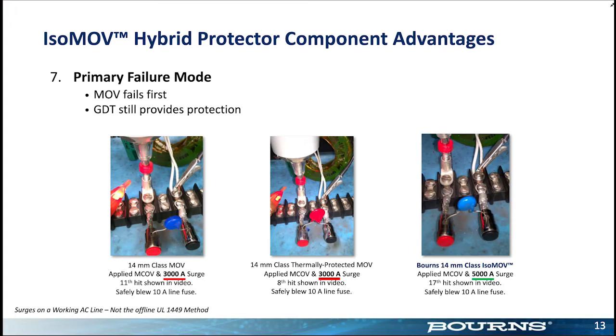So now I'm going to show another movie with the three components, and this time we're surging it, right? The other movie was temporary overvoltage. I increased the AC line. This is with a 120 volt line, and we've superimposed surges on top of it. First, I'm going to show a normal MOV. You surge it at 3 kA, and you keep surging it. And finally, on the 11th hit, you'll see it flame out.